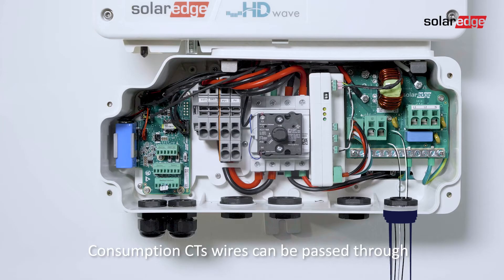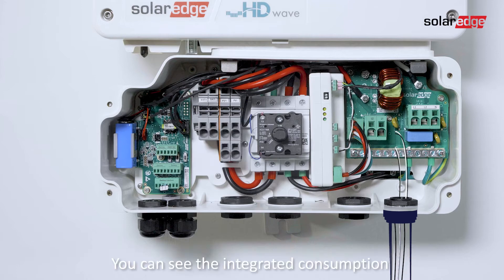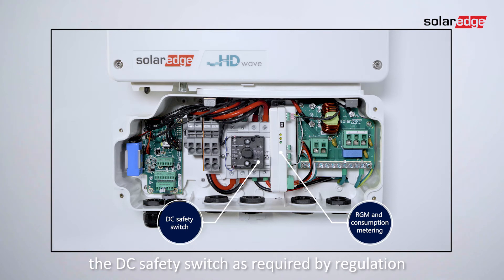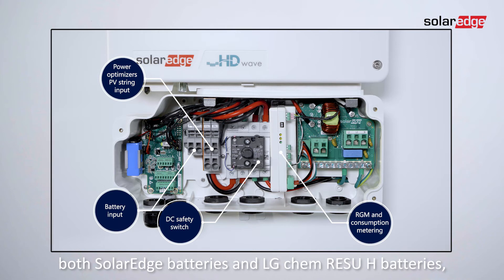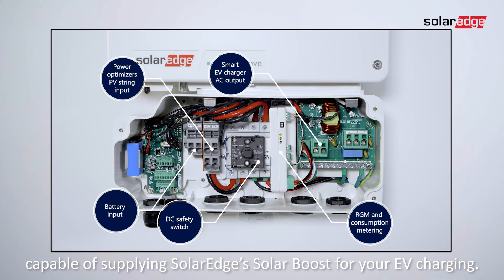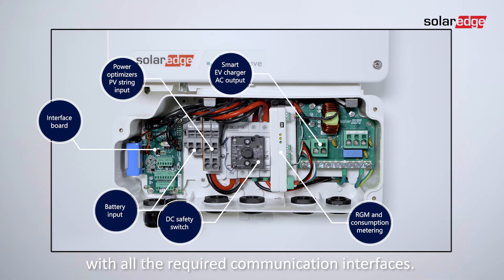Consumption CT wires can be passed through the same AC conduit according to the application note. You can see the integrated consumption and revenue-grade production meter, the DC safety switch as required by regulation, power optimizer's PV-string inputs capable of up to 200% PV-oversizing, battery inputs to support both SolarEdge batteries and LG CHEM RESU-H batteries, the smart EV charger AC output capable of supplying SolarEdge's solar boost for your EV charging, and lastly, the interface board with all the required communication interfaces.